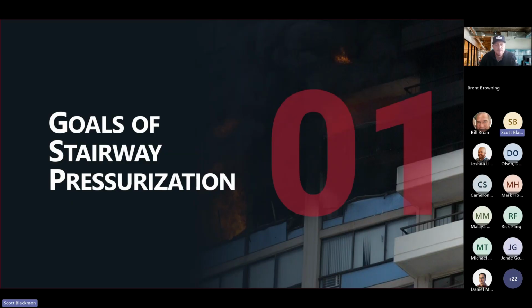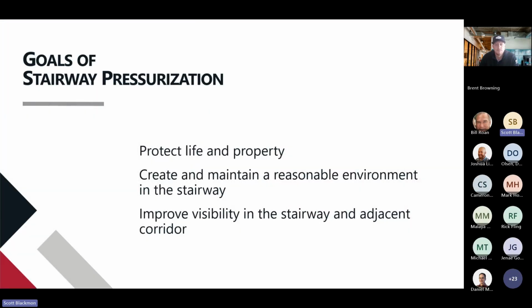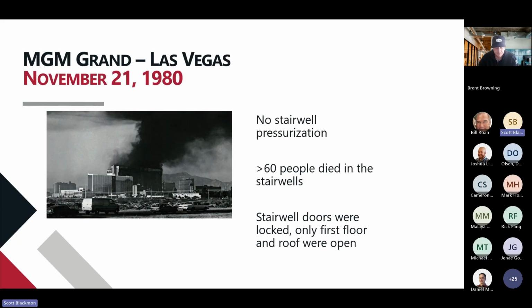So the goals of stairwell pressurization are pretty simple. It's to protect life and property. It's basically to make a tenable environment for people to escape in case of a fire in a building. A lot of this stemmed from the MGM Grand Fire that occurred in 1980. It was a relatively small fire, occurring on the first floor, but due to a lot of design oversights, over 60 people died in the stairwells, and it was all due to smoke inhalation. There were no actual fire-related deaths.